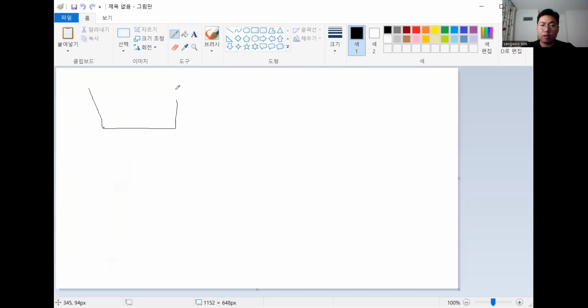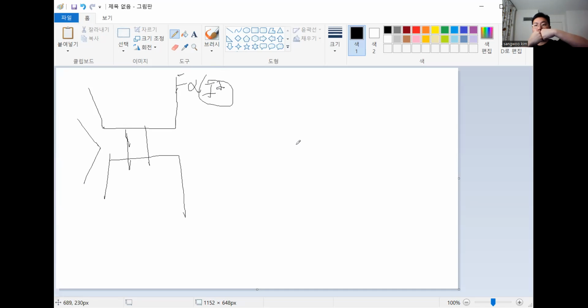Look at that. Here at the contactor, repulsion force happens, right? Because the magnetic force is proportional to the current squared, between them a slight bouncing happens. We say arcs happen.